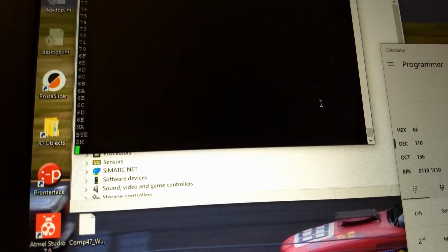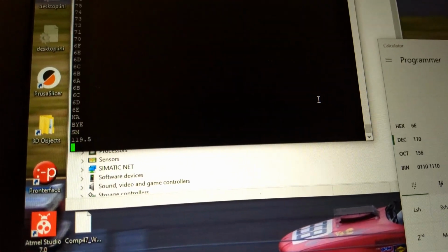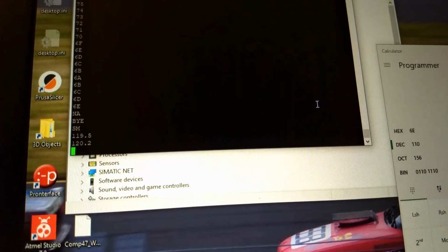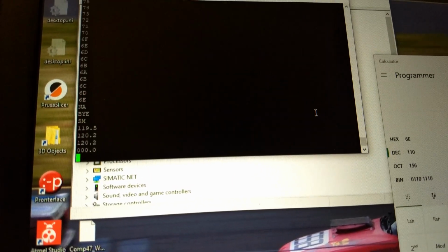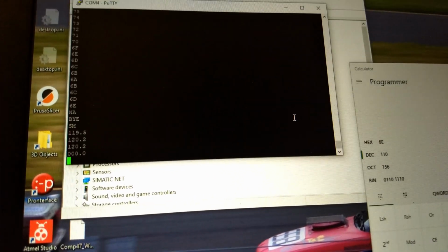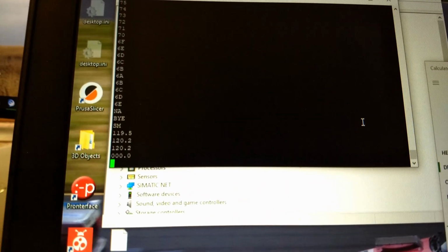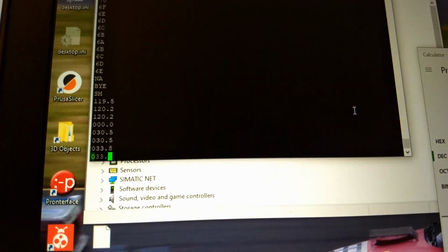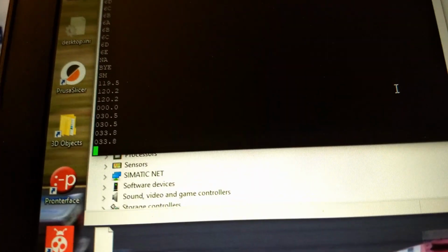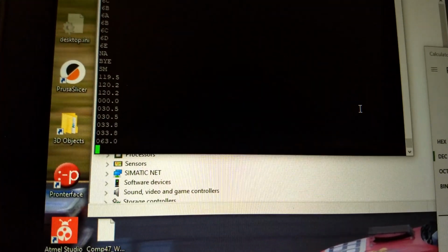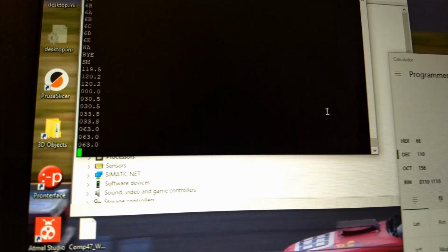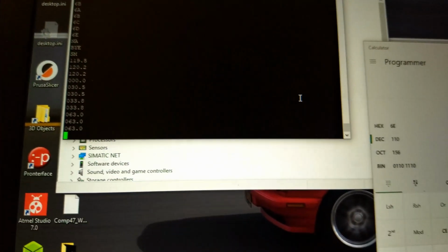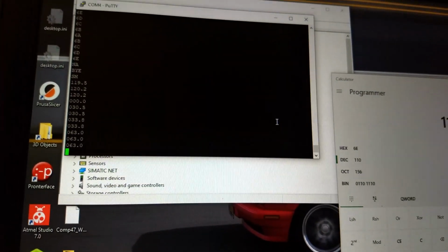So now we can come back into smart mode. We can look at our line in voltage, our line out voltage, yep, and we can see shift P gives us zero because we've got nothing. And now if I turn it on to setting one, shift P now reports as 30%, 33, right in that area. And if I kick it up to the high setting, which was overloaded before, shift P, it only reports as 63. So we've successfully scaled these values by half.